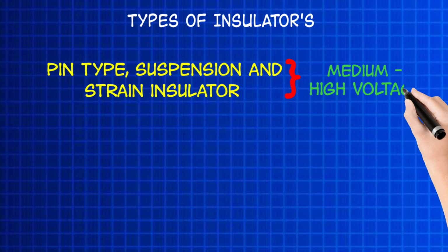In an 11 kV system, we typically use one part of an insulator made from a single piece of porcelain or glass. In higher voltage system like 33 kV or 66 kV, manufacturing of one part of porcelain pin insulator become more difficult. The higher voltage thicker insulator and very thick single piece porcelain insulator is not practical to manufacture.